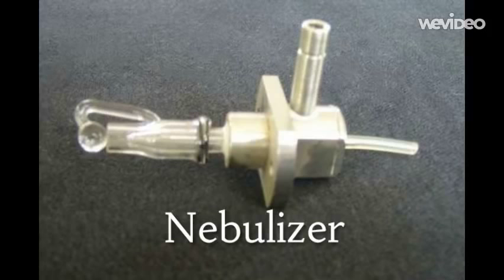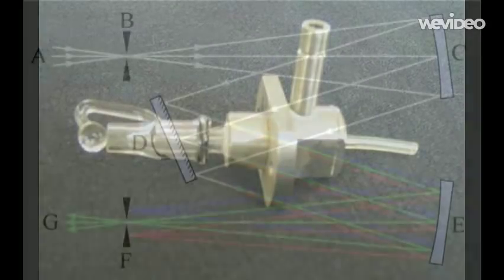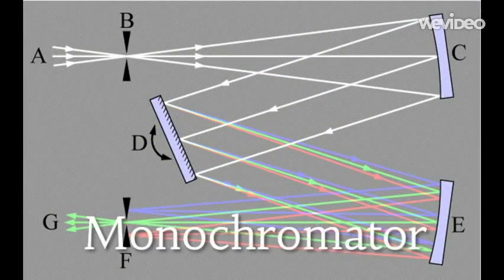The aerosol, fuel, and oxidant are mixed thoroughly for introduction into the flame source. The monochromator isolates the analytical line photons passing through the flame, and ensures that only a narrow spectra of light impinges on the photomultiplier tube.